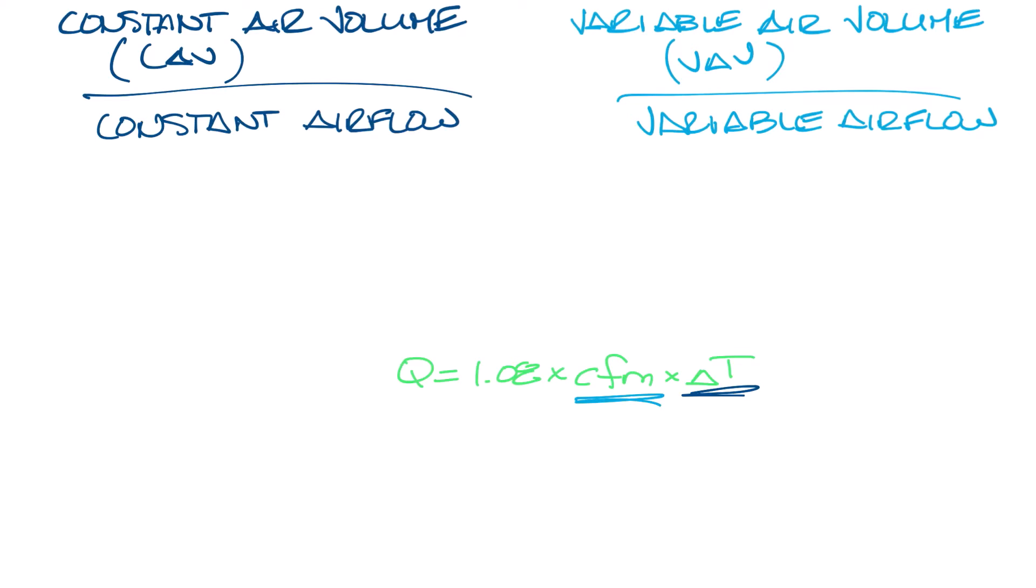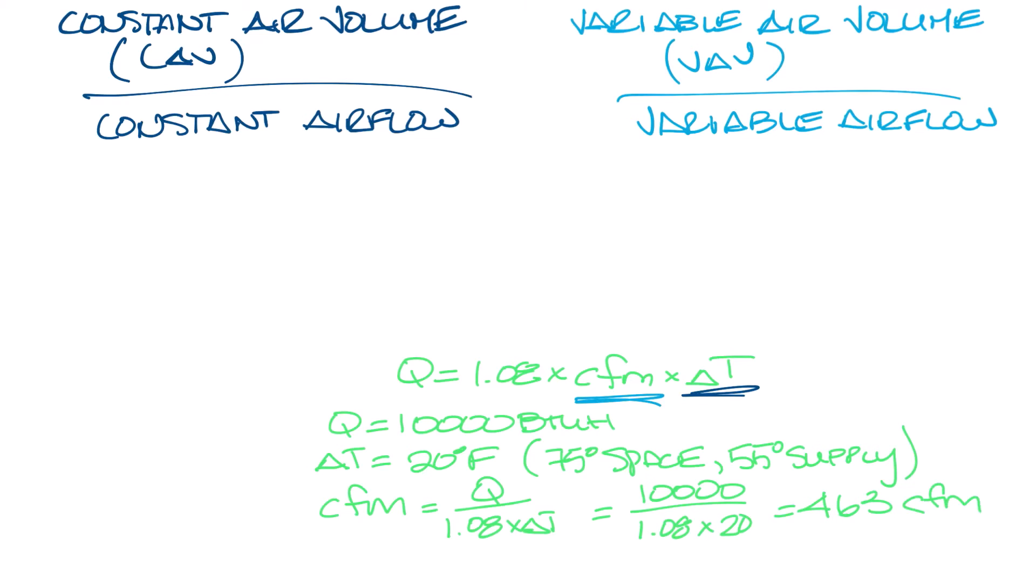So for easy math, let's say that we have a load in the space of 10,000 BTU. In a VAV system, delta T is typically 20 degrees Fahrenheit based on a 75 degree space temperature, which gives you a 55 degree supply air temperature. So now we can calculate how much CFM we need, where CFM equals Q 10,000 BTU divided by 1.08 times delta T. So that gives us 10,000 BTU divided by 1.08 times 20 gives us 463 CFM.